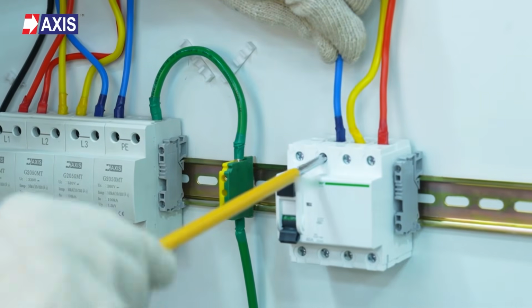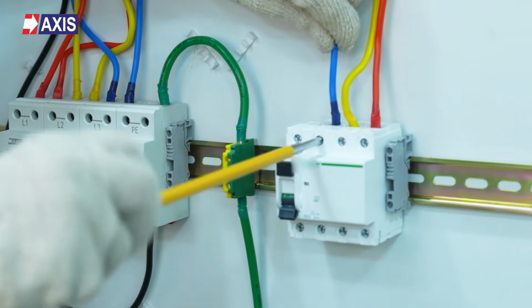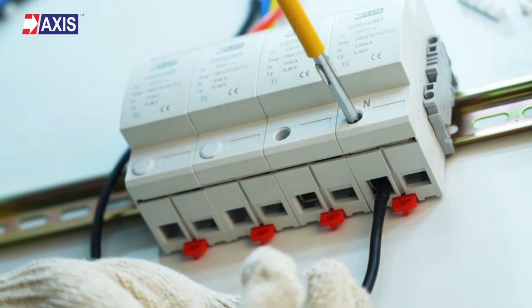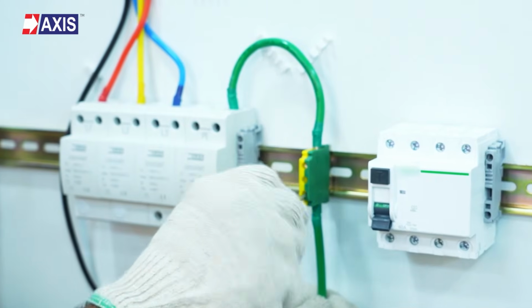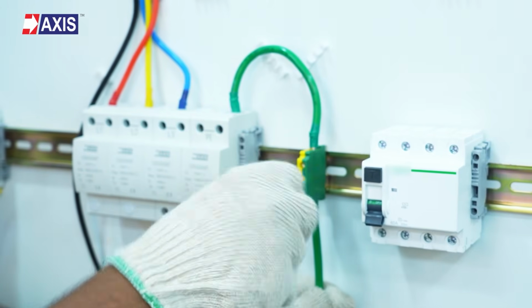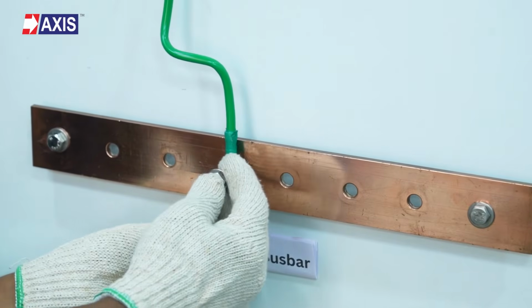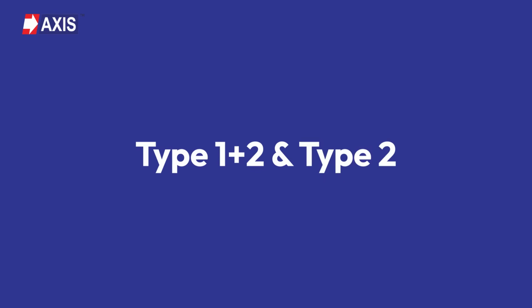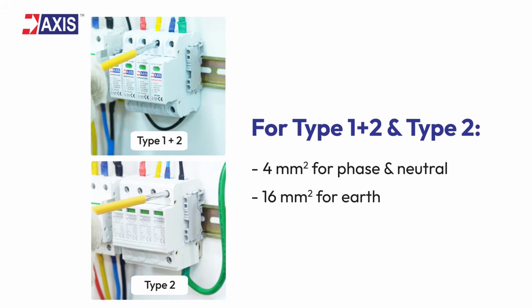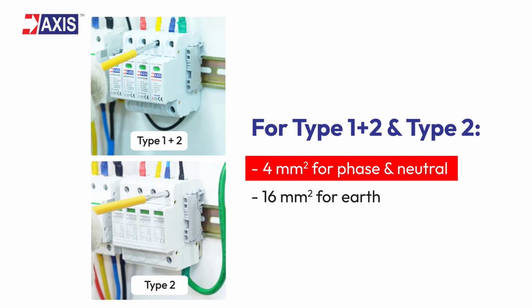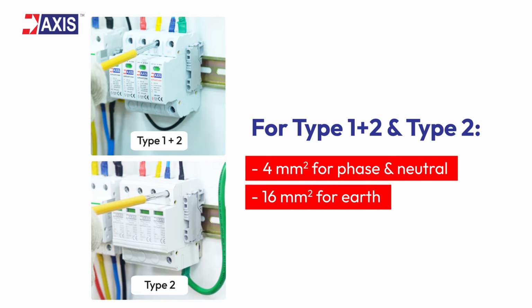Connect the 3-phase wires red, blue, yellow. Connect the neutral wire to the neutral terminal. Connect the earth wire to the earth terminal marked PE. Next, we will install Type 1 plus 2 and Type 2 SPD in the same manner. But for them, we will use the cable size of 4 square mm for phase wire and neutral wire and 16 square mm for earth wire.